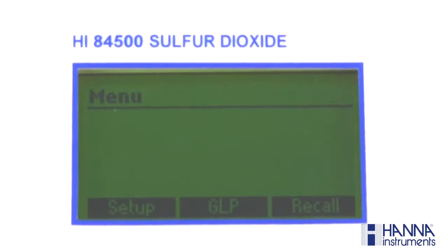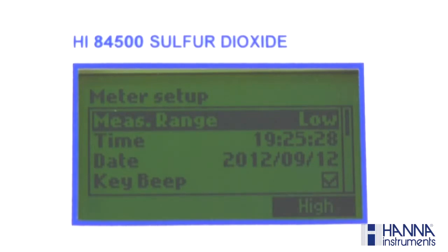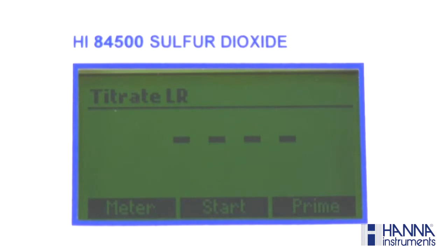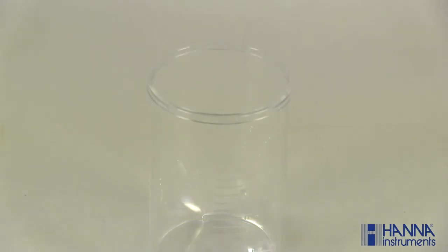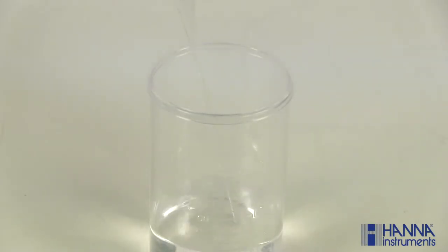Press Menu and select Setup to choose your range. We'll be measuring low-range free sulfur dioxide today. Again, you want to make sure that you have the correct titrant and that you've primed with the correct titrant as well. Using a clean pipette, precisely add 1 ml of HI84500-55 calibration standard to a clean 100 milliliter beaker. Fill the beaker up to the 50 milliliter mark with DI water.